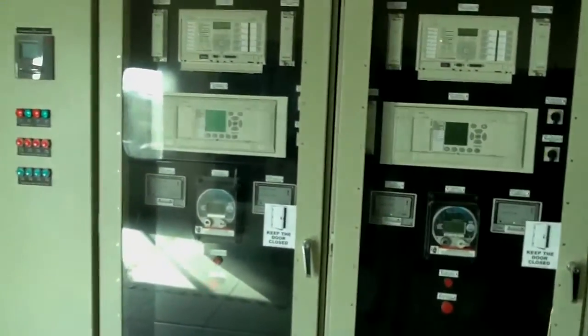These are the remote control panels. These are basically when we energize our 132 kV, it has 5 switchgears, right? One is for the Nuriyabad line, one is for the complete line circuit, one is the bus coupler, and 2 are for the power transformer.